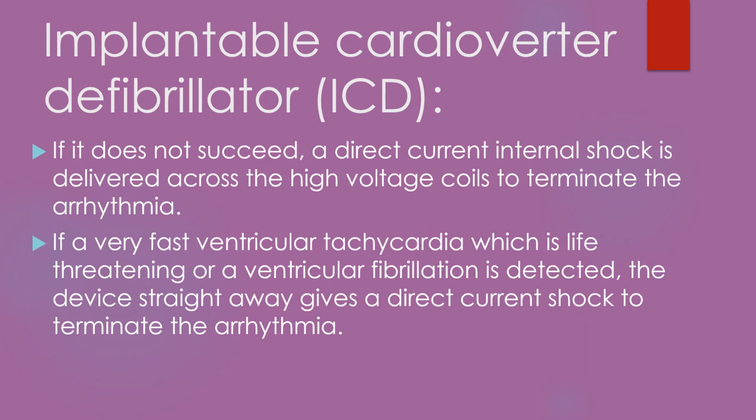If overdrive pacing does not succeed, a direct current internal shock is delivered across the high voltage coils to terminate the arrhythmia. If a very fast ventricular tachycardia which is life-threatening or a ventricular fibrillation is detected, the device straightaway gives a direct current shock to terminate the arrhythmia.